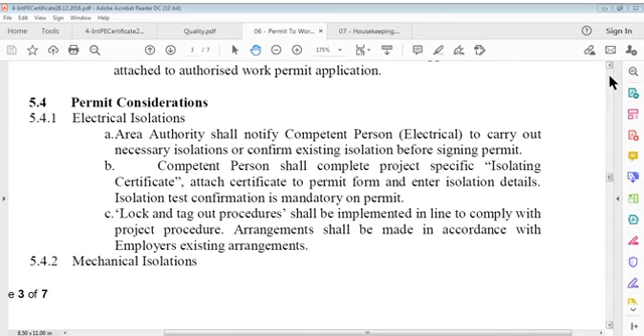Electrical isolation: the area authority shall notify the competent person, that is electrical, to carry out necessary isolations or confirm existing isolation before signing the permit. Though we discussed this, I am just refreshing it. The competent person shall complete the project specific isolation certificate, attach it to the permit form, and enter isolation details. Isolation test confirmation is mandatory on the permit. Lock and tag out procedures shall be implemented in line with project procedure, and arrangements shall be made in accordance with the employer's existing arrangements.